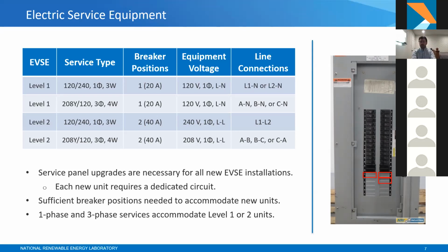You can see each one of those red rectangles corresponds to a breaker position, and that holds, say, 1 breaker slot. For level 1 units, you need a single breaker position, and typically a 20 amp rating is sufficient for most EVSE units. And that's where you have different line-to-line connections here. These are things you can work with your facility manager to make sure that you're having these installed correctly, but it's always great to have an electrician work on these and perform the installations correctly. But in terms of scoping out your service panel's capacity available, it's really just important to make sure that you have sufficient breaker position capacity.